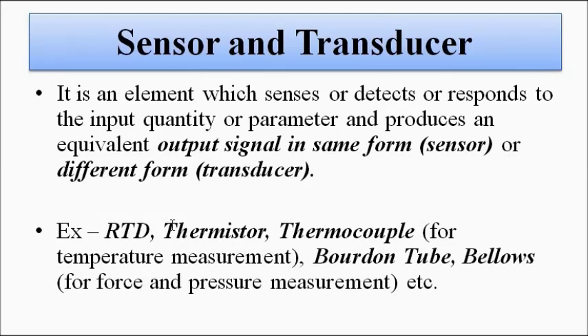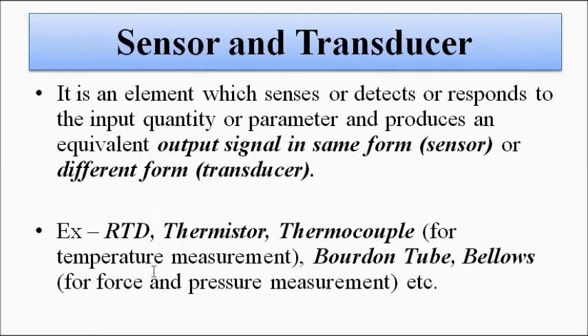The sensor or transducer detects any change in the parameter of interest. For example, for temperature measurement we can use RTD, thermistor, or thermocouple. For RTD and thermistor, temperature change is converted into resistance change; for thermocouple, temperature change is converted into a potential difference. For force and pressure measurement, we can use a Bourdon tube or bellows, in which force or pressure is converted into linear or angular displacement. Various other instruments employ various types of sensors and transducers.